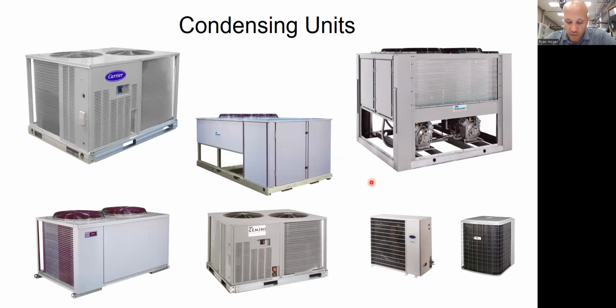And by the way, we only call it a condensing unit if it's an AC version. Once it becomes a heat pump version, which looks exactly the same as these things, we no longer call it a condensing unit because that coil outside is a condenser coil, and then in the heating mode, it's an evaporator coil. So calling it a condensing unit becomes weird. There's also the term condensing unit and condenser, and some people use those interchangeably. Condensing unit, properly speaking, would imply that it has a condenser coil, a condenser fan, and a compressor. A condenser would just be the condenser coil and the condenser fan and no compressor.